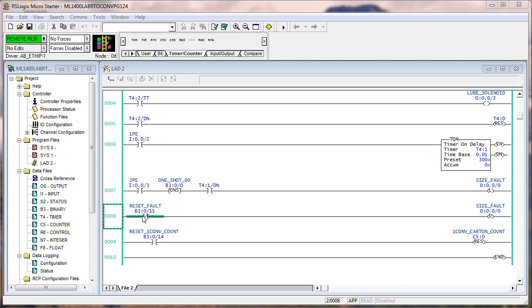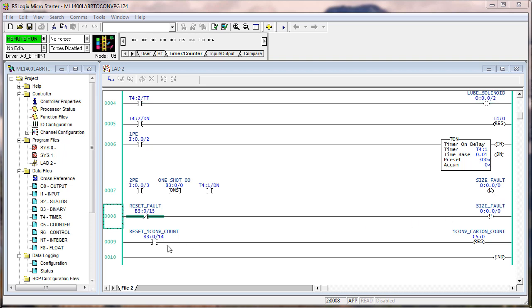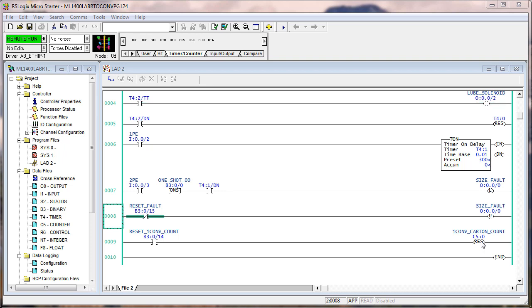Another thing that we did was I took this, which was the stop push button. I had to change it to reset fault. I might have used different text reset button. But anyway, use B3 0 slash 15 to unlatch the size fault. And then B3 0 14 to reset counter 5. And this would be typically used on an HMI where there was a jam or things got messed up. So they pulled all the cartons off of one conveyor. Then they hit a button on the screen that clears the count. So it basically resets the system to a clean slate.